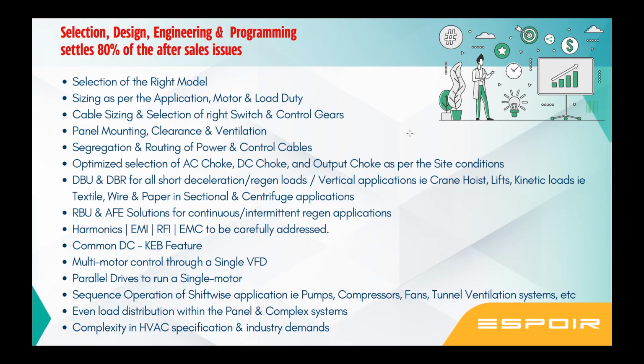So when you select a VFD for these vertical applications, you need to be very, very, very careful. There are logics available. You need to program and tune these parameters of releasing the brake only after sufficient torque is generated and the brake is mechanically released. If the brake is released and the torque is not generated, it can create an accident. If the brake is applied and you start running it, it will create noise and it can trip on an overload. So these aspects we need to be really careful about.